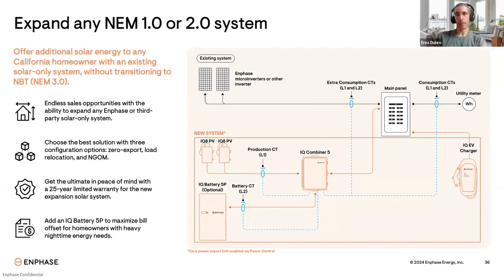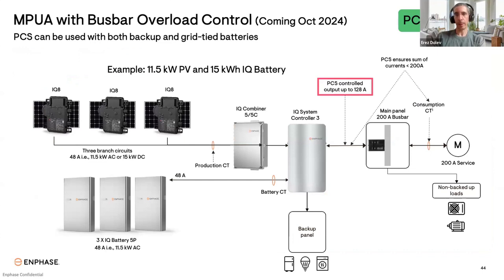And he has a follow-up question about the combiner 5. He's saying, perfect. So this adjustment can happen virtually with any IQ combiner 5 or 5C install. Yeah. And I do want to mention one important thing that I forgot to mention earlier, which is that for Busbar PCS, it's important that the consumption CTs are installed on the main feeders to that main panel. Now, there are instances where that's not possible or it's very difficult. Just physically, there might not be any space, or the way that the wires come into the main panel, it's just not physically possible to put the CTs on the main feeders. In those cases, we can't use Busbar PCS. It really needs to be an accurate measurement of the total amount of current flowing through the main panel.